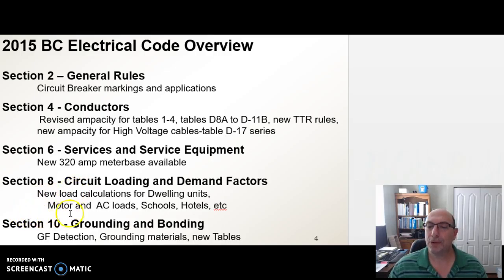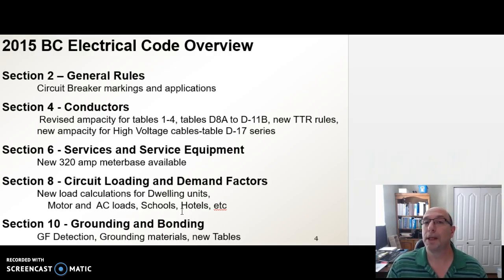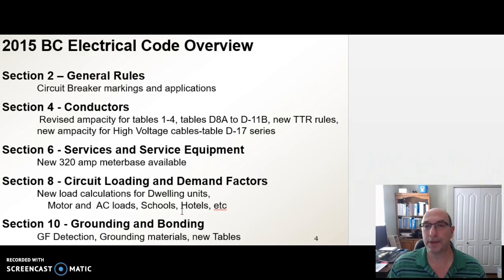Big change in Section 10, grounding and bonding. You know that you have to install your grounding conductor in copper — that is the number one choice. But you can use aluminum, with restrictions, so be very careful. You are not allowed to bury aluminum grounding conductor underground — that has to do with moisture and corrosiveness. You can use aluminum grounding conductor, but it must be above ground with no moisture conditions.